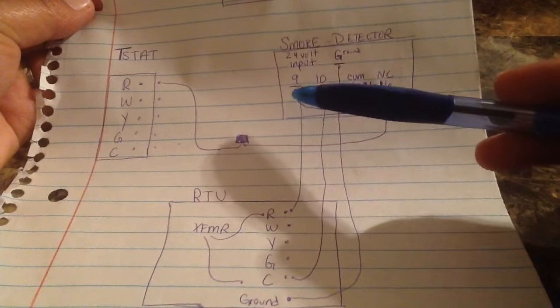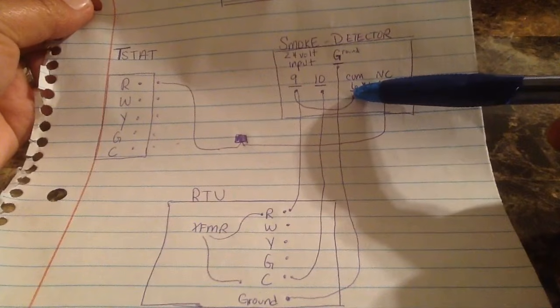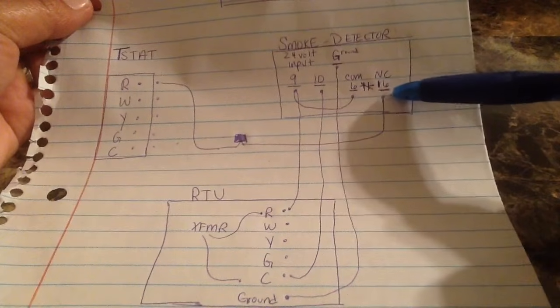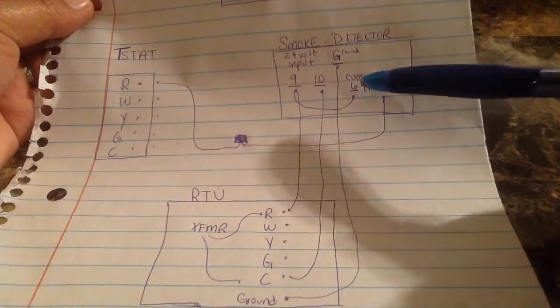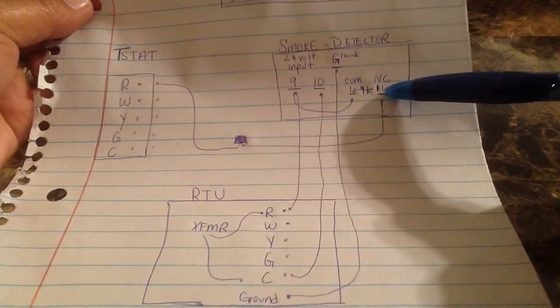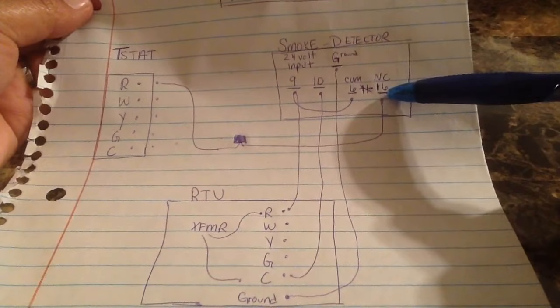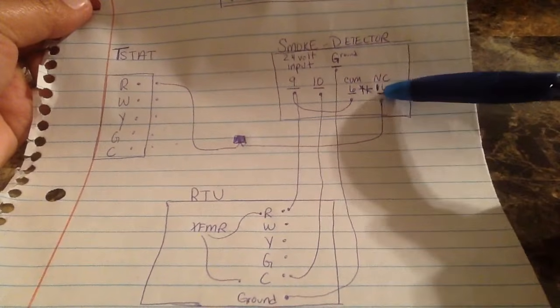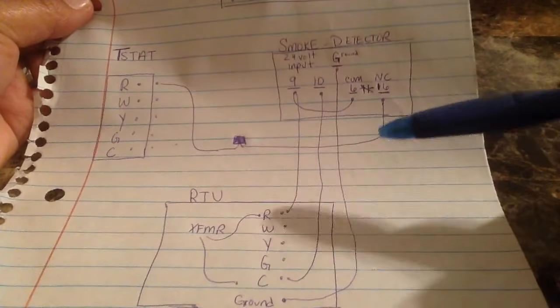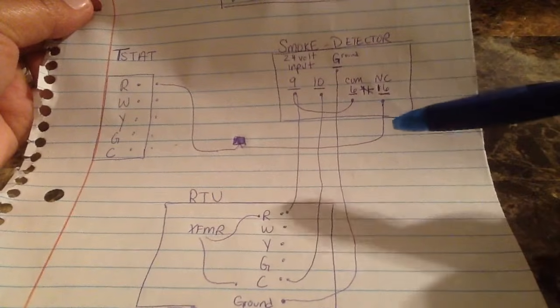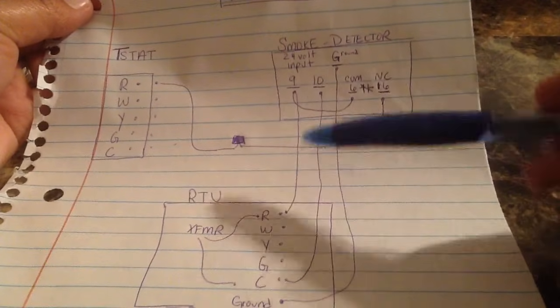And then what we're going to do is we're going to put a jumper between terminal nine and six, which is common. And typically you're going to have a normally closed or normally open switch to six. We use the normally closed switch which is labeled typically number sixteen, and then sixteen we're passing it back out to R at the thermostat. So we're breaking R at the thermostat, and then of course you have your ground.